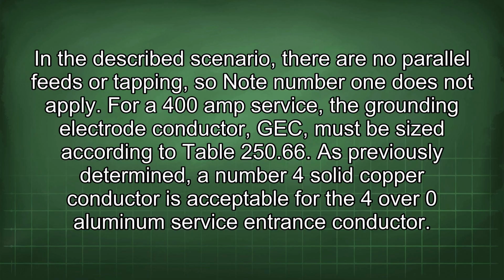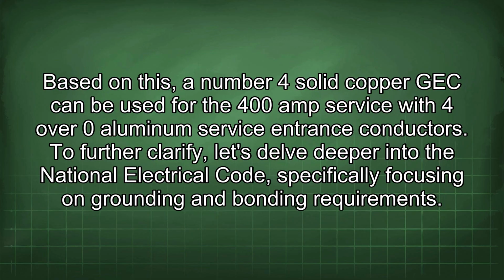For a 400 amp service, the grounding electrode conductor, GEC, must be sized according to Table 250.66. As previously determined, a number 4 solid copper conductor is acceptable for the 4/0 aluminum service entrance conductor. Based on this, a number 4 solid copper GEC can be used for the 400 amp service with 4/0 aluminum service entrance conductors.